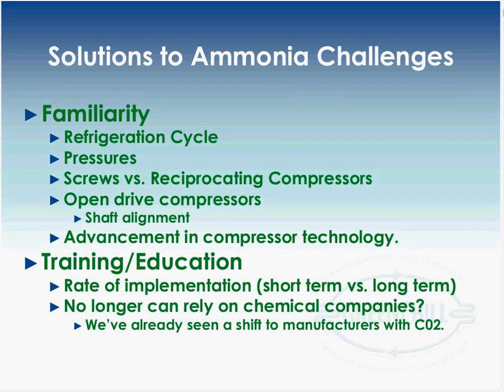Familiarity is another hurdle that was brought up. As far as familiarity goes, ammonia is going to be used in the same refrigeration cycle, and the pressures are actually going to be very similar to an HFC system. The contractor is going to be in his ballpark of what he's thinking for pressures. We use reciprocating compressors just like we do now in supermarkets. Screw compressors can also be used, but they're better suited for larger applications. There's an in-depth subject on when you'd use a screw over a reciprocating compressor, but it just needs to be noted that reciprocating can be used and probably will be the tendency in the commercial systems that come out.